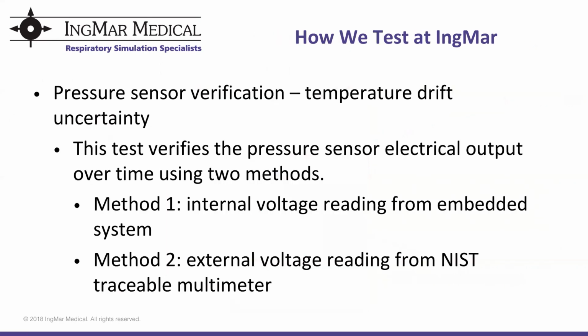So now I'm going to go through each of the different tests that we perform with a high-level explanation of how the test works. The first test we call pressure sensor verification, temperature drift uncertainty. The importance of this test is to assure the temperature fluctuations within our embedded system do not affect the outputs from our pressure sensors. The cylinder pressure sensor is the single most important device in the ASL as it measures the airway pressure to start the breathing algorithm.